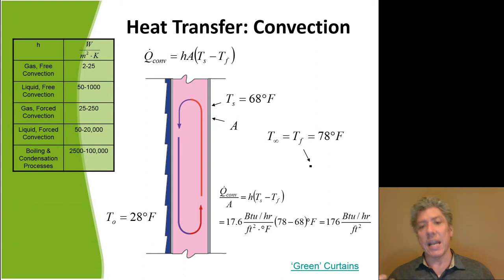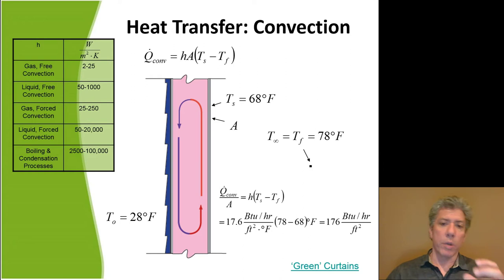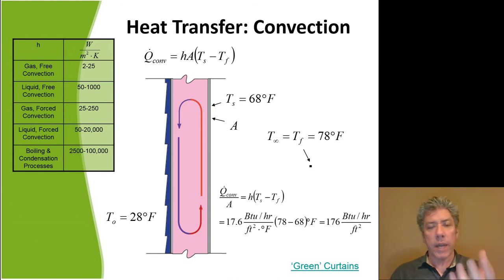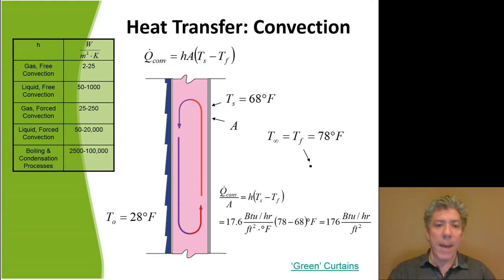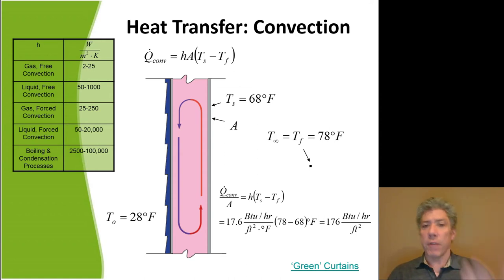If you think about gas with free convection — the first row in the table — the typical convective heat transfer coefficients are from 2 to 25 watts per square meter per Kelvin. By free convection I mean any gas — air, nitrogen, combustion gases — where the fluid moves not because you've pushed it with a fan but simply because as it warms it becomes more buoyant and rises in the gravity field.